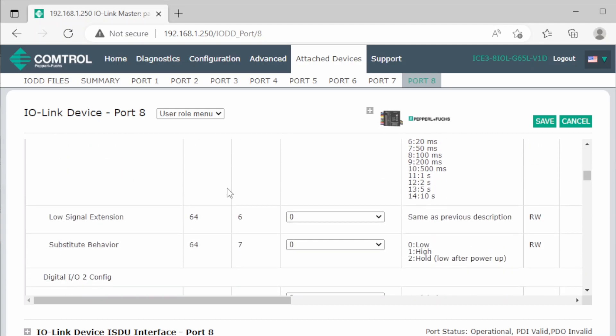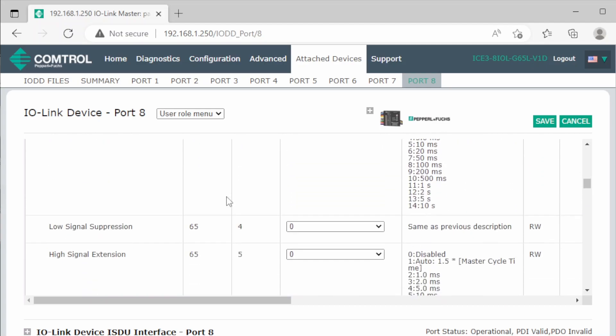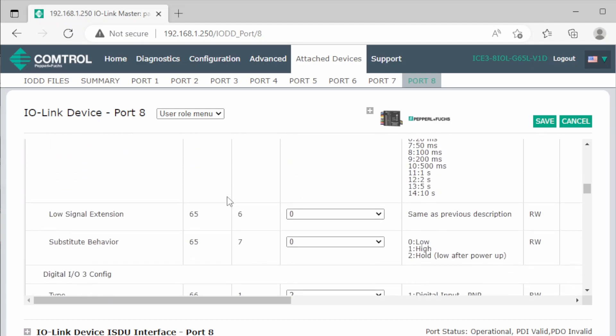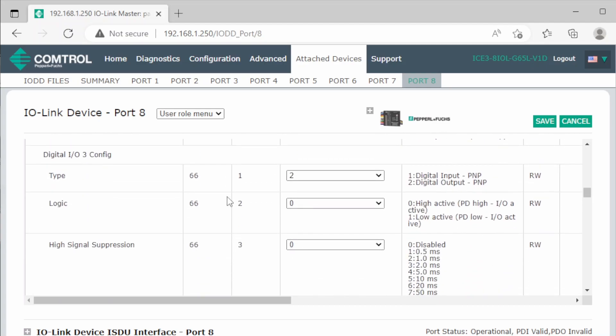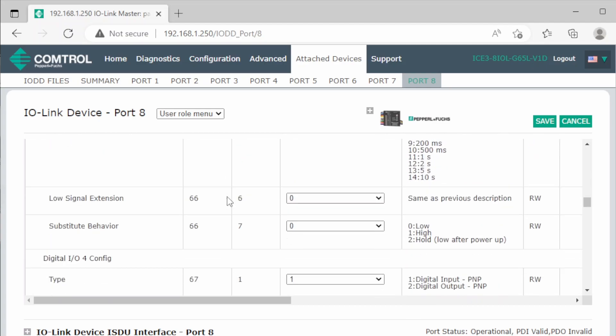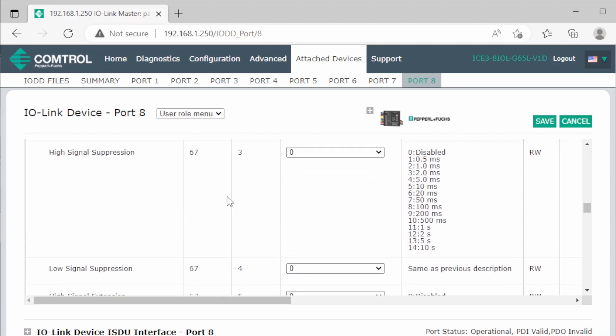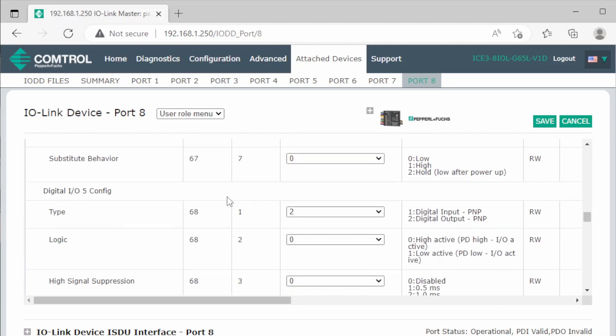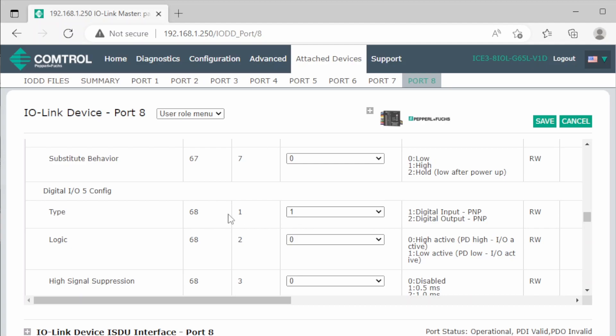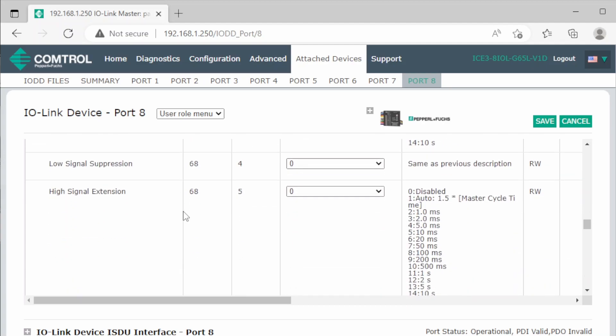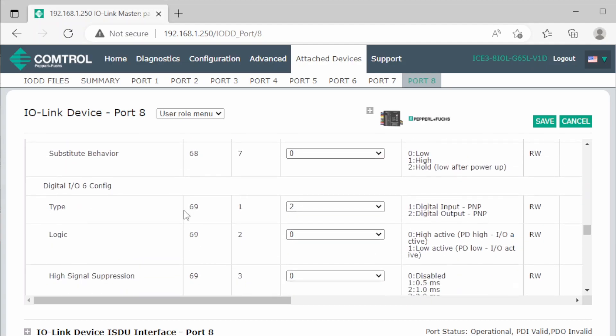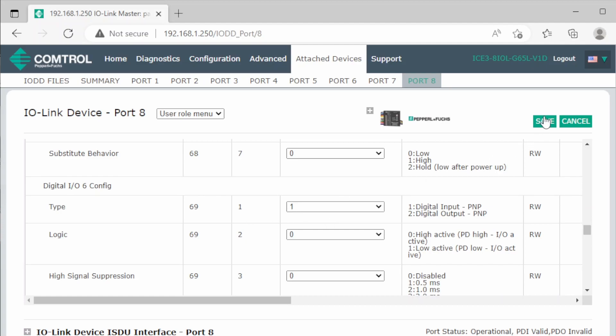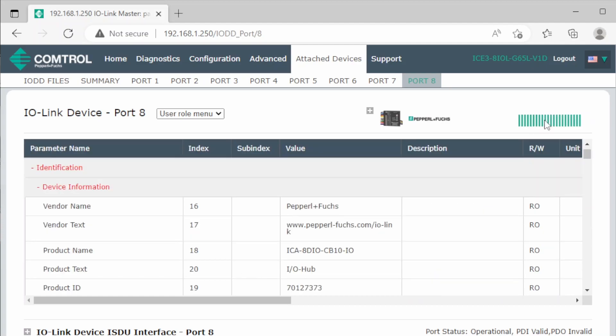But for number 5 and 6, we want to set it as an input, because I've already connected a button to that wire. So we will make that a 1. And also for the next one, we set it as a digital input. And then we press save, and we are done with the configuration on the IO-Link master.